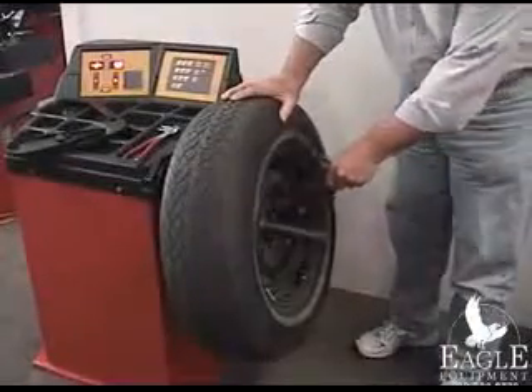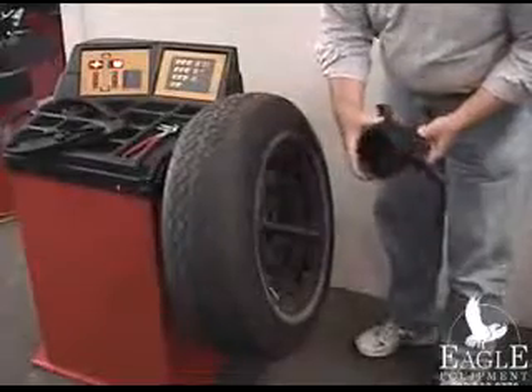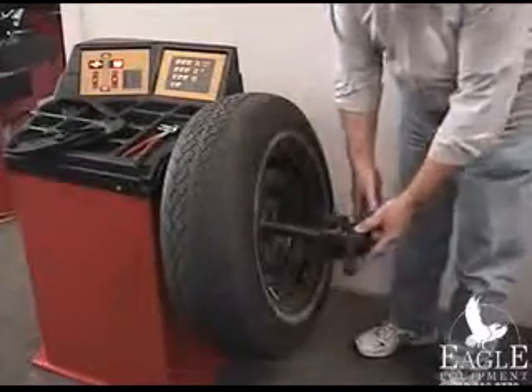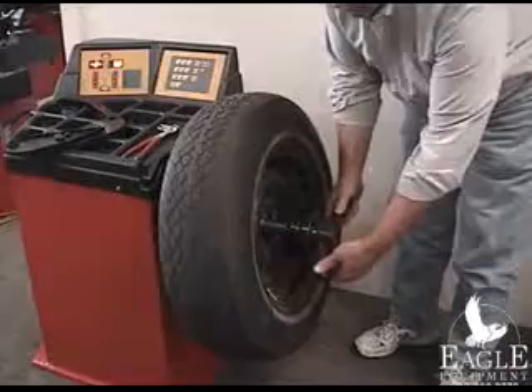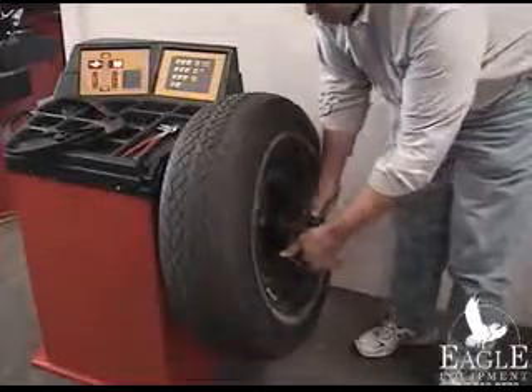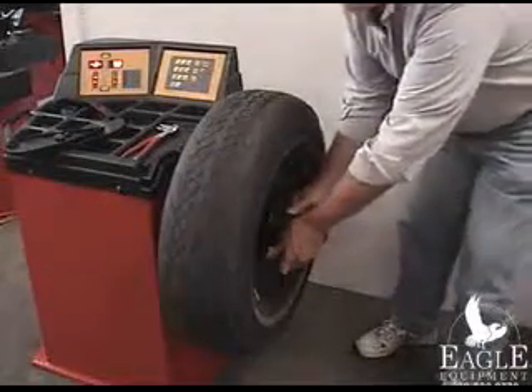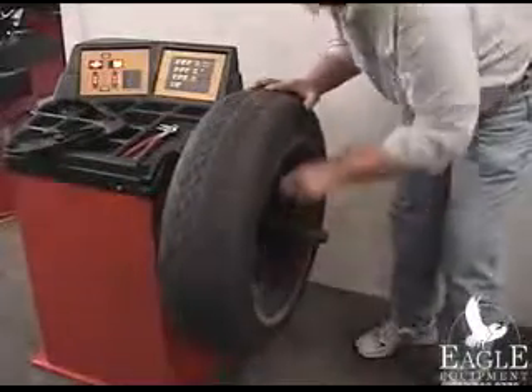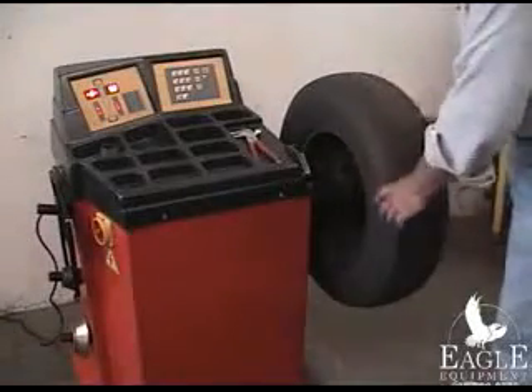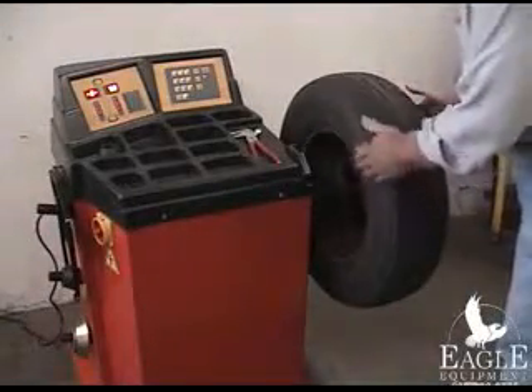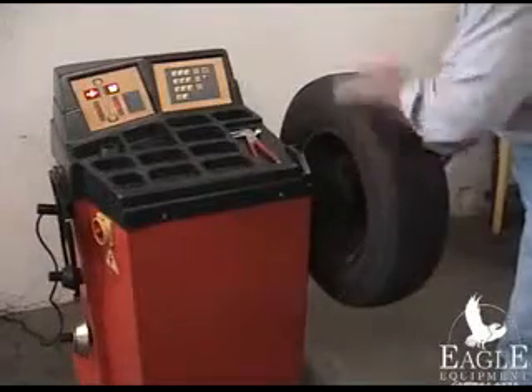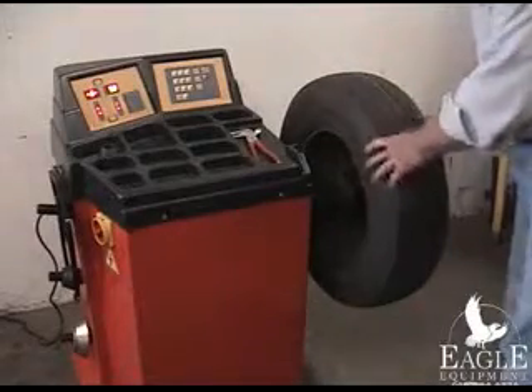When you mount the wheel with the cone on the inside, you need to use the plastic cup on the speed nut. Speed nut on the shaft, push the red tabs, the nut will go in as far as it can go by hand. The rest of the way you thread the wheel on the machine. After you mount the wheel, make sure that it's mounted properly. Give it a few turns, make sure it doesn't wobble, doesn't move up and down, so that you have it centered right on the machine.